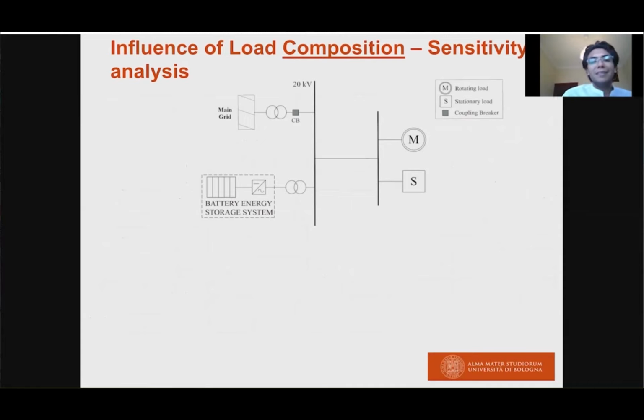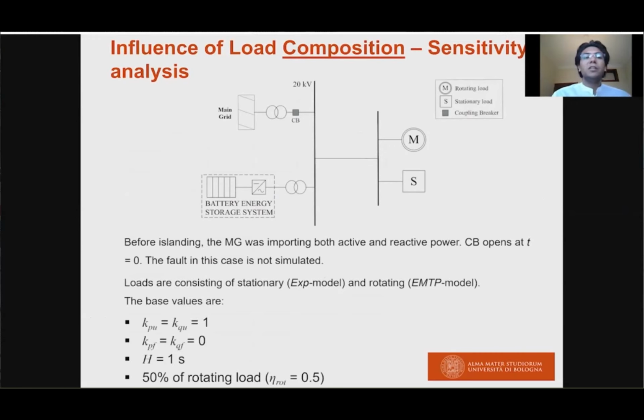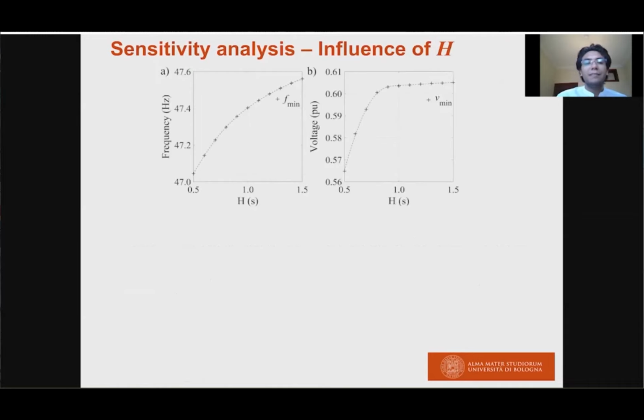Okay, the second analysis studies the influence of the load composition. First of all, we carried out a sensitivity analysis, as I already said at the beginning of this presentation, considering a simple system with just one battery and a combination of rotating and stationary loads. In this case, the fault is not simulated, and the circuit breaker is supposed to open, initiating the islanding transition. The load is represented by our considered benchmark, so I'm referring to the EMTP model plus exponential model, and the base values for the loads are these. We start varying them one by one and see what happens.